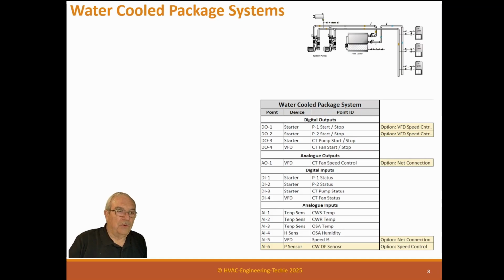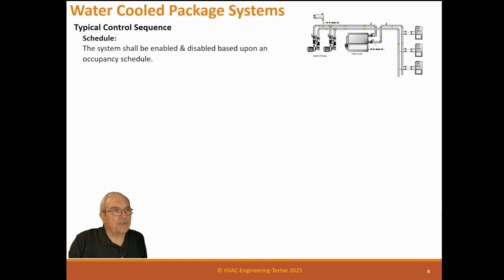So you want to rely on the network to gather a lot of data and give you stuff that you can use. It's interesting, but it's not critical. Otherwise, if it's critical, like speed control, I always put hardwired points, and if they want a net connection, we'll bring in a network connection on top of it. Those are the points for a water-cooled package system. All right, let's look at the sequence.